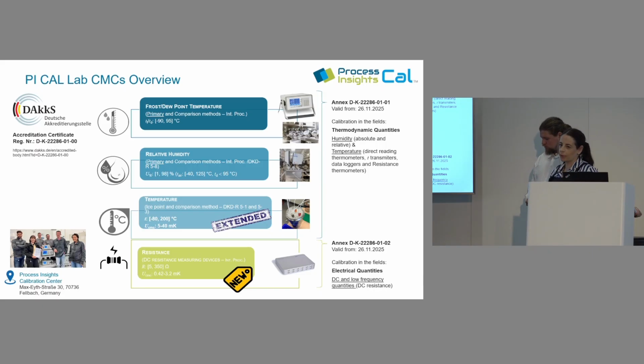We are also accredited to calibrate DC resistance measuring devices in the range of 5 to 350 ohm with quite a good uncertainty, 0.42 up to 3.2 milliohm. So we are able to give traceability to all our instruments, the T12, if you know it, this temperature measuring bridge, and this new product that my colleague will introduce to you.